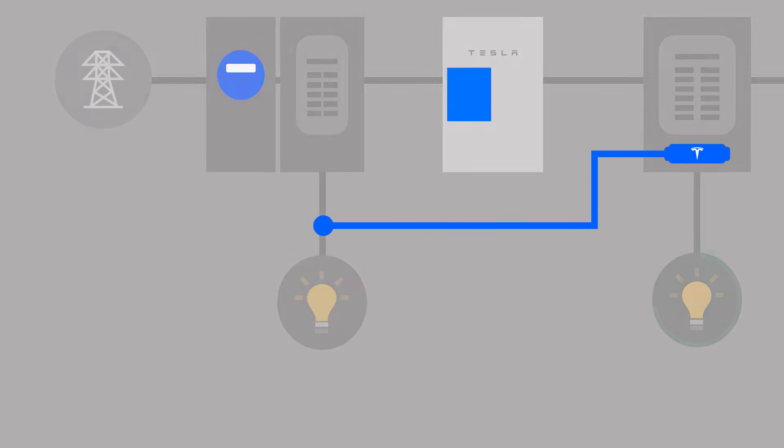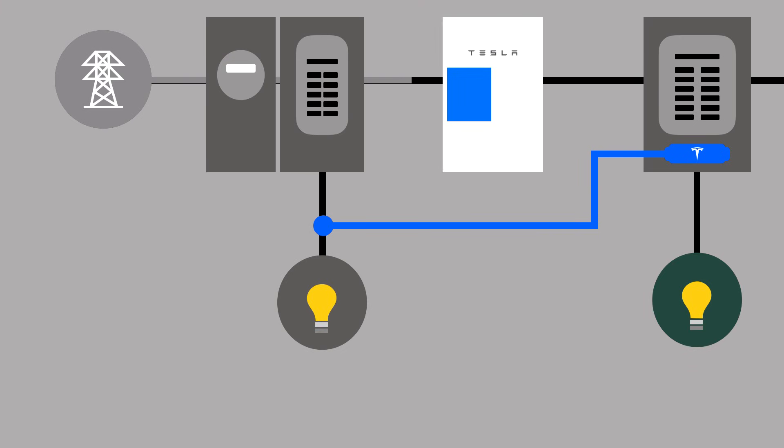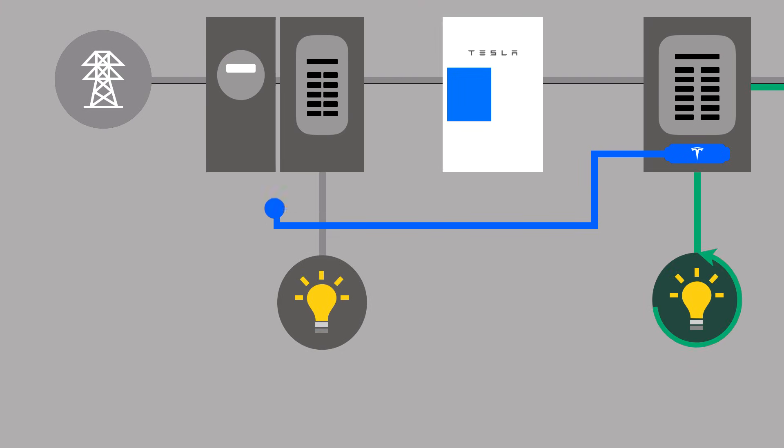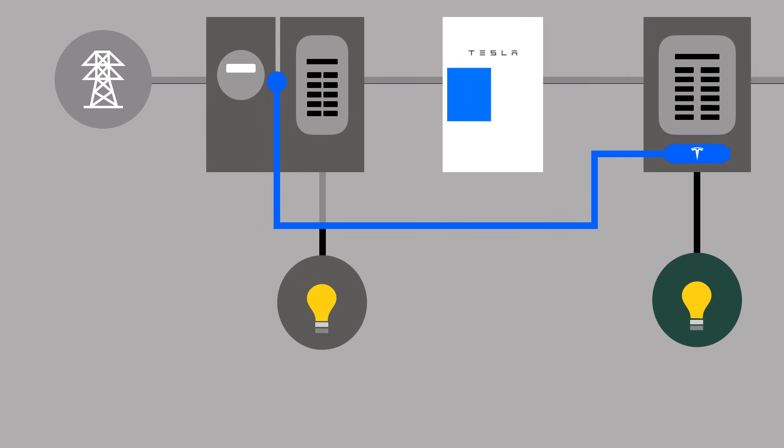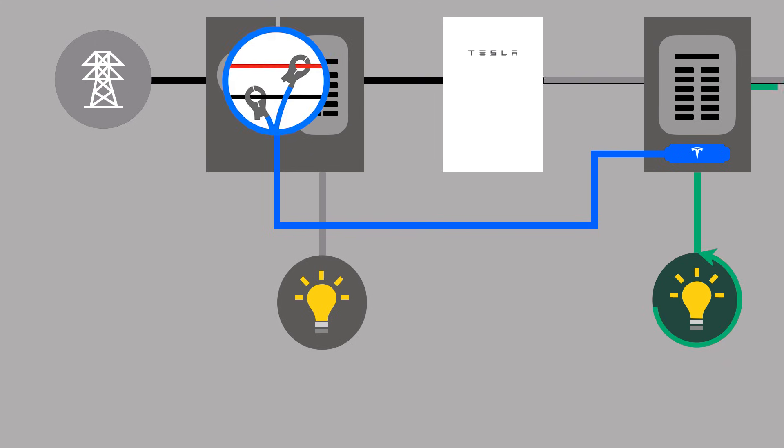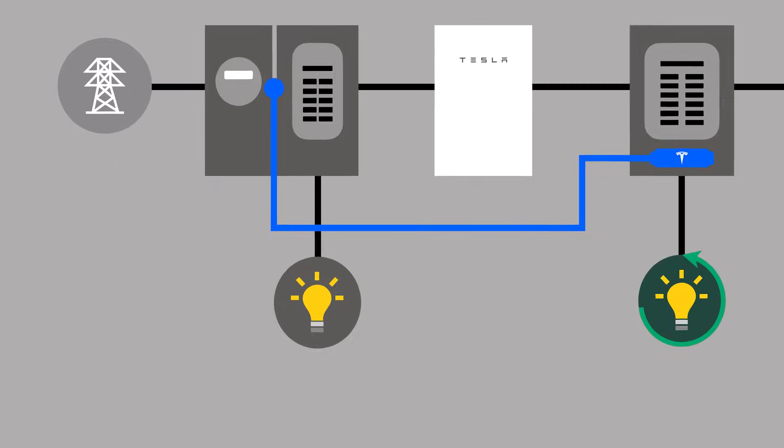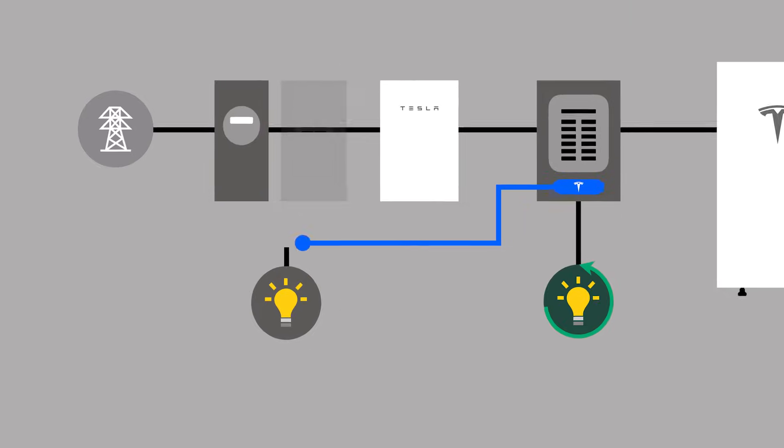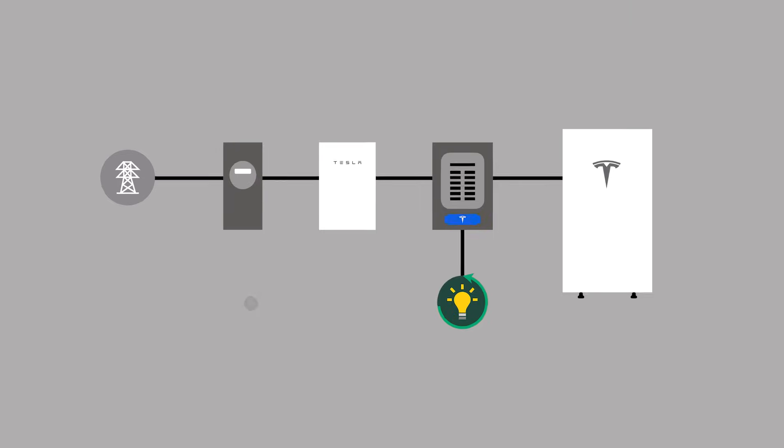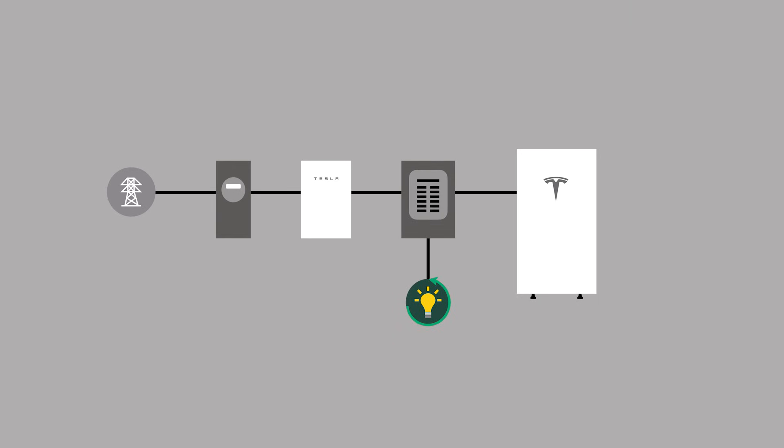Another option is to use the Tesla remote energy meter to monitor the feeders to the main panel without using the site meter integrated within Gateway, again, with one current transformer on each line. Both options provide the system with the site reading that is equal to the amount of power flowing in and out of the home.